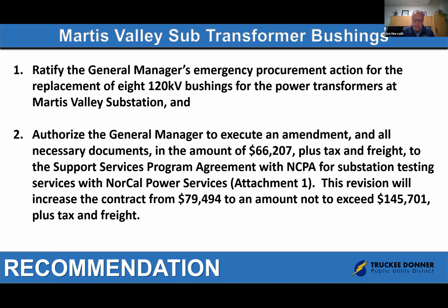It is staff's recommendation that the board ratify the general manager's emergency procurement action for the replacement of 8 120 kV bushings for the power transformers at Martis Valley Substation, and authorize the general manager to execute an amendment and all necessary documents in the amount of $66,207 plus tax and freight to the Support Services Program Agreement with NCPA for substation testing services with NorCal Power Services, included as attachment 1 to the staff report.